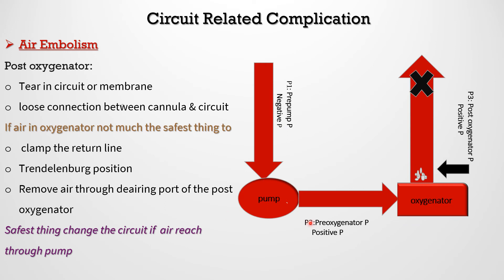The most dangerous effect of air embolism occurs when air is post-oxygenator. This may be due to a tear or crack inside the membrane itself, or disconnection between the return cannula and the circuit. First, clamp the return line to prevent air reaching the patient. If air remains inside the oxygenator, aspirate it through the post-oxygenator ports. If air has exited the post-oxygenator and is near the return line to the patient, clamp the line, place the patient in Trendelenburg position, and remove the air through the post-oxygenator deairing port. If this cannot be done, proceed with a circuit change.